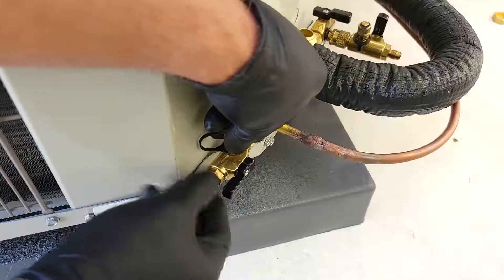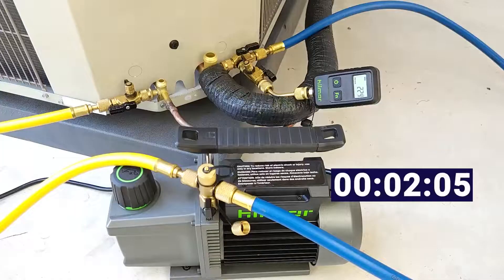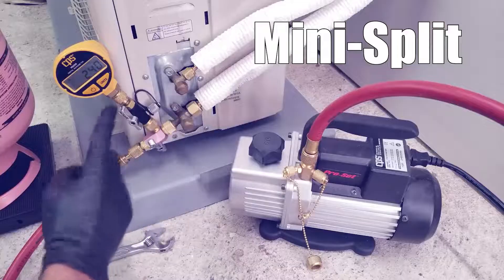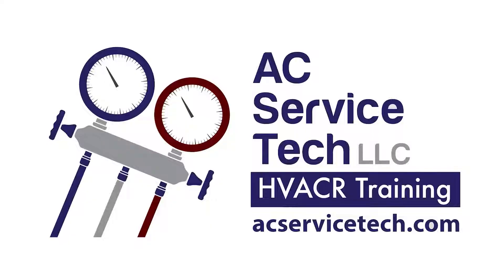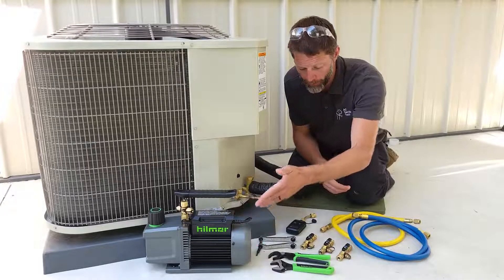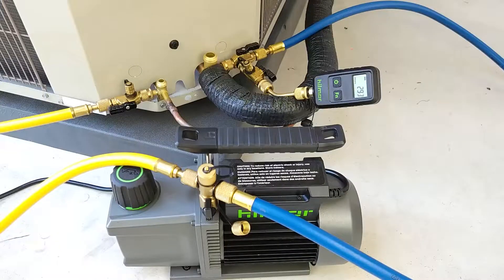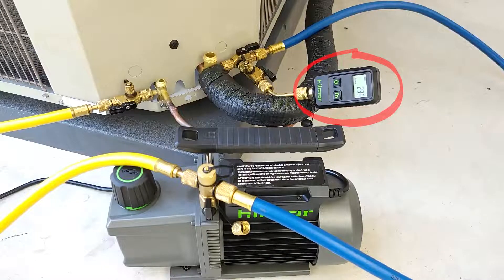In this HVACR training video, we're going over how to pull a vacuum on an air conditioning system step-by-step in order to allow refrigerant into the tubing. We're going to be pulling a vacuum without a manifold gauge set, using only two hoses, our 5 CFM vacuum pump from hilmor. We're also using a digital vacuum gauge, so we'll be able to see incremental changes in our vacuum as we're removing air, nitrogen, and water vapor out of the system.